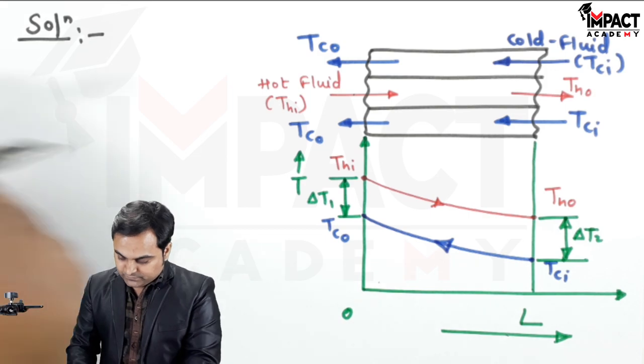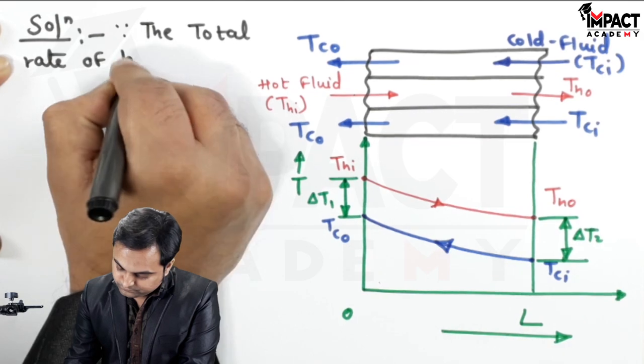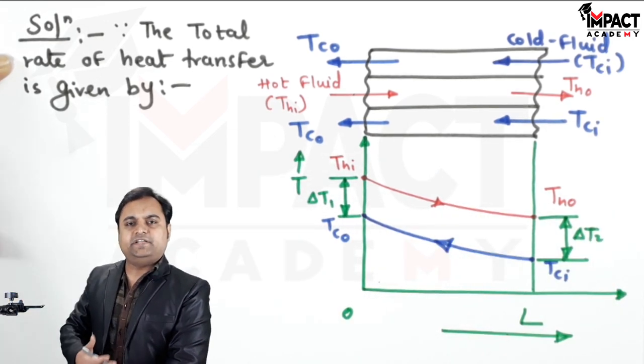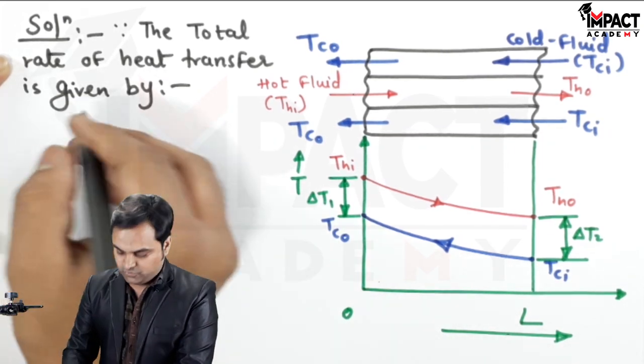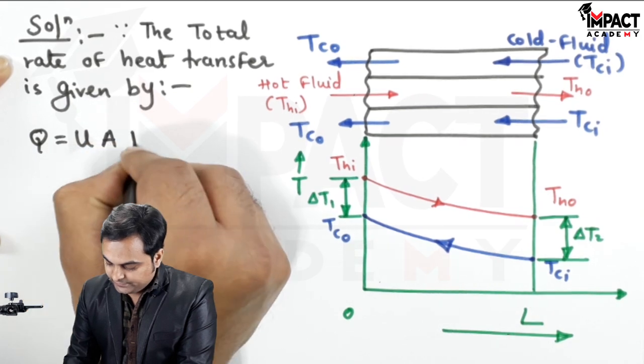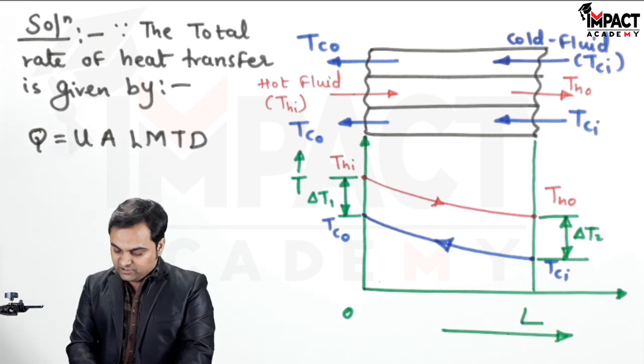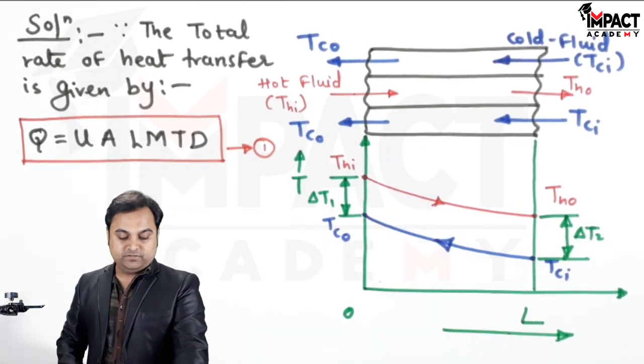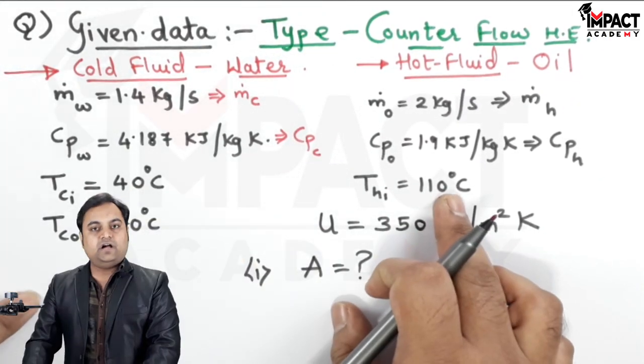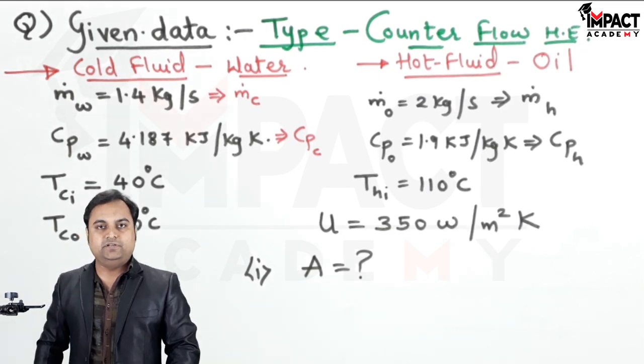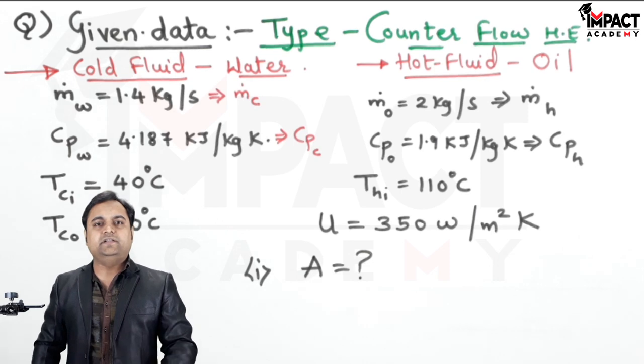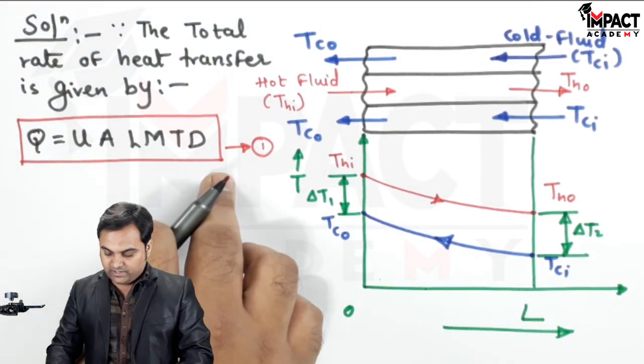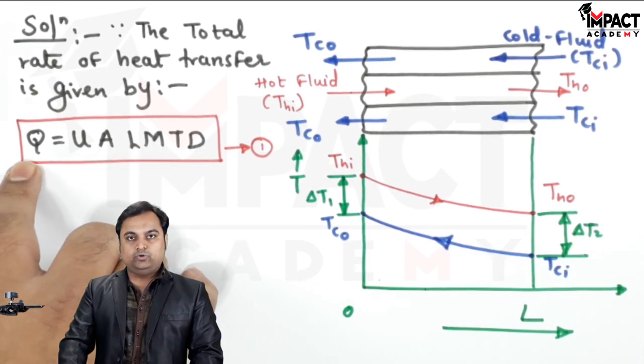The total rate of heat transfer for a heat exchanger — whether parallel flow or counter flow — is given by Q = U·A·LMTD, using the LMTD method. We use LMTD because three out of four temperatures are known. If only two temperatures (typically the inlet temperatures) were given, we would use the NTU method instead.